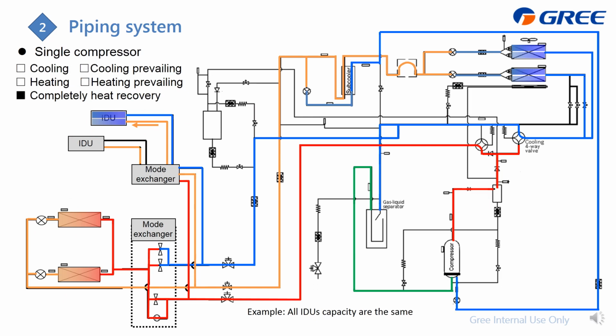The last is the completely heat recovery mode. That means the refrigerant just makes the cycle between the indoor units, the indoor unit requiring heating and the one requiring cooling; they are almost the same. And in this case, we just make this one to be cooling. And then similar to this one, we just send the gas back to the mode exchanger and then to the outdoor unit. Also for this outdoor unit, just pay attention here.